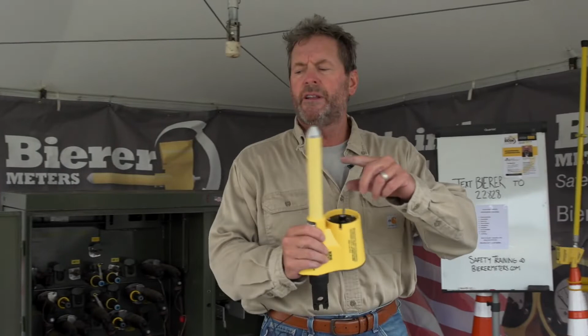Care: when you're using these tools, understand that every one of these products, the voltage indicator phasing tools, have a line limit right here. ASTM wanted us to put a line limit. What that does is let the user know that you do not want to bypass that line limit with a potential ground or another hot phase.